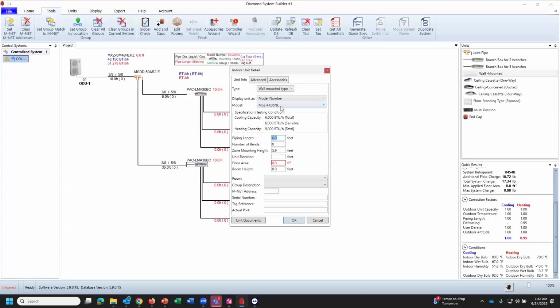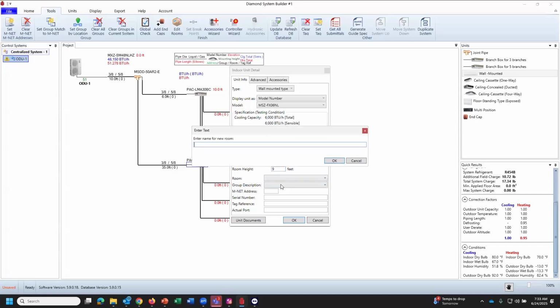So we're going to do a couple of FS06s coming off the branch box to this first one. We're going to go 12 feet, no bends. Unit elevation is going to be at 8 feet. Floor area in this room, let's call it a 10 by 10 room, so we've got 100 square feet. Room height is going to be 9 feet. And we can call this bed 1.